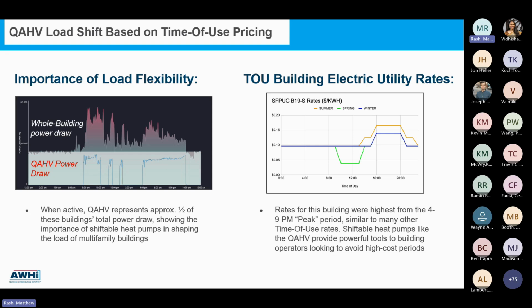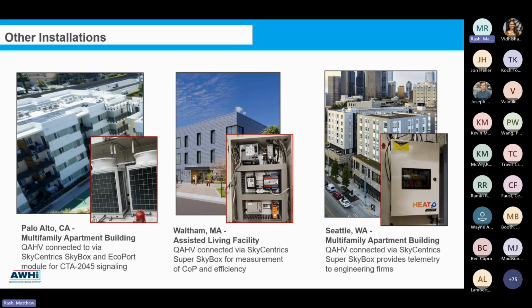That's a little bit different from the version 1 that some folks may have been familiar with in the limited test markets. We've expanded that for the lead-lag control and staging, but that also has options for demand response with an additional device from SkyCentrics. And Tristan is available on this call. He provided some slides. The SkyCentrics folks have been involved with some of these pilot projects, early projects that I mentioned in limited test markets. So I threw in a couple slides here to summarize where they've utilized this product along with the SkyCentrics for demand limiting, load shifting, I should say.